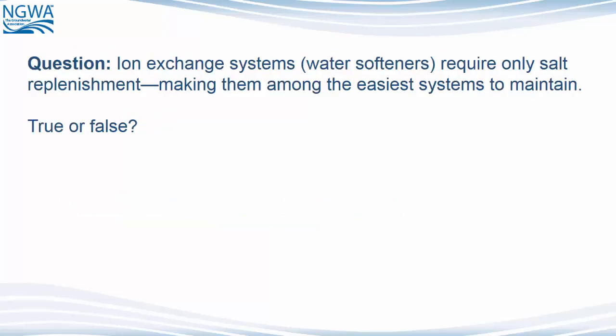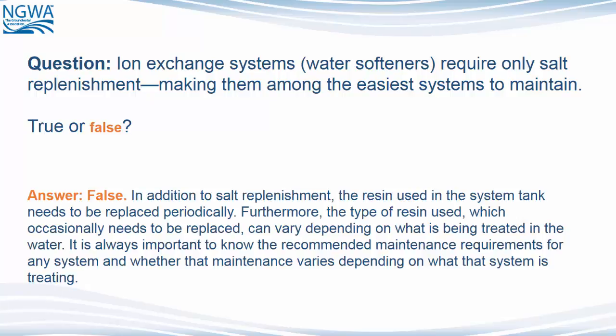Question: Ion exchange systems or water softeners require only salt replenishment, making them among the easiest systems to maintain. True or false? The answer is false. While these systems are easy to maintain, in addition to salt replenishment, the resin used in the system tank needs to be replaced periodically. Furthermore, the type of resin used can vary depending on what is being treated in the water. It is always important to know the recommended maintenance requirements for any system and whether that maintenance varies depending on what the system is treating.